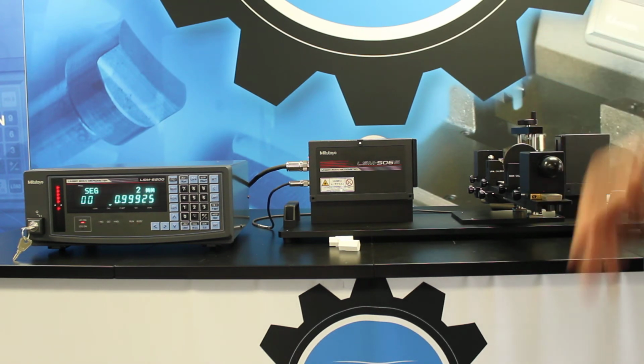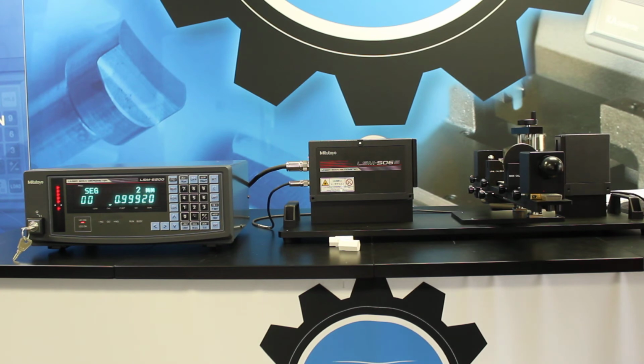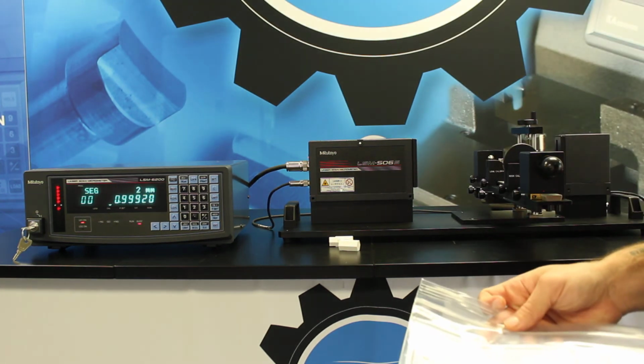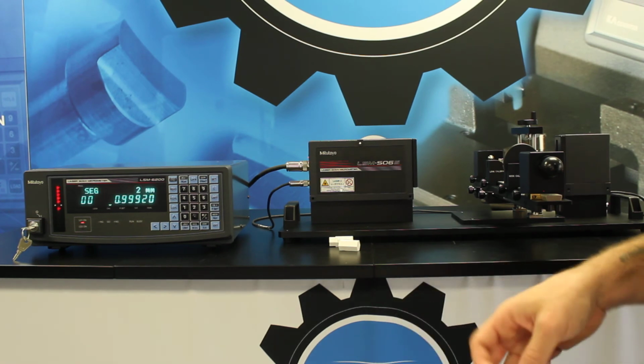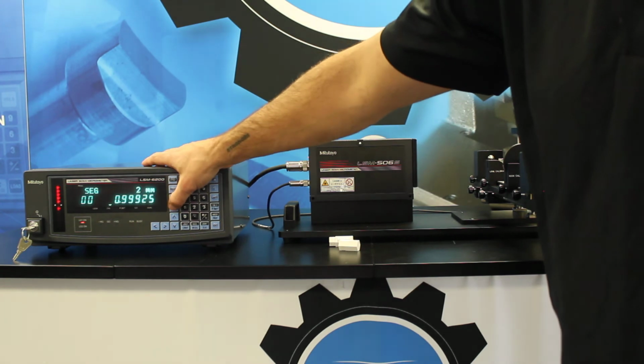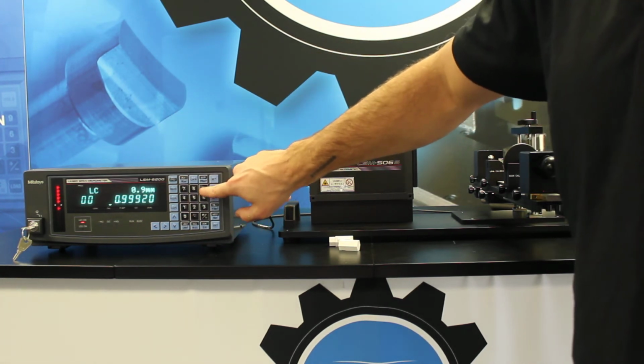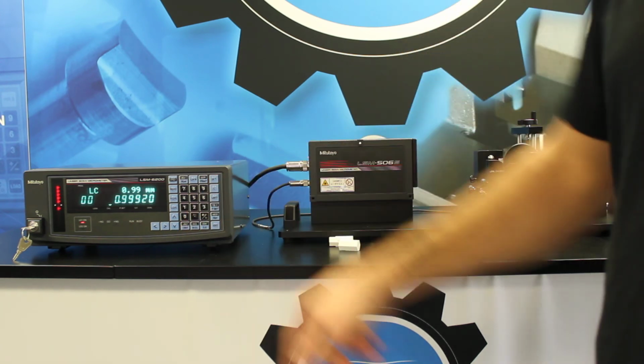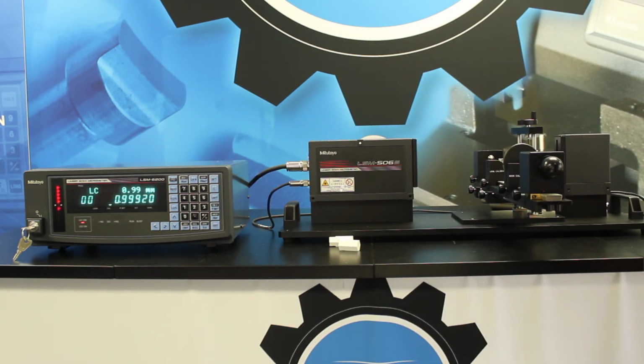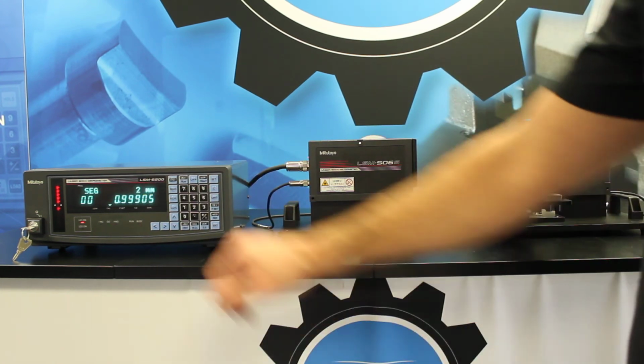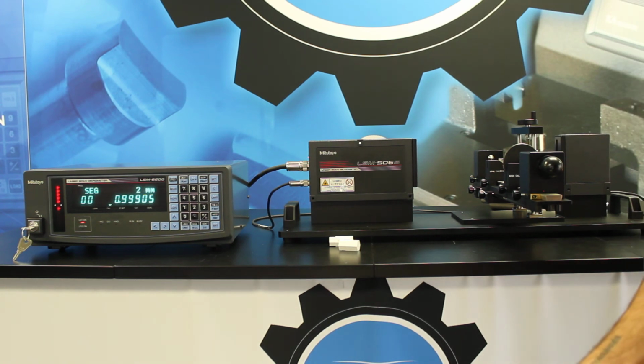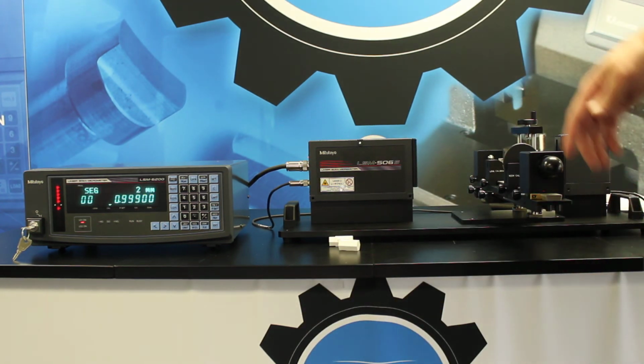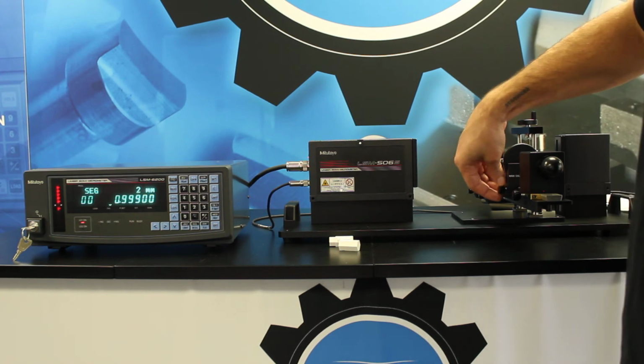I do not need to raise or lower my work stage at this point for the low calibration artifact. My low calibration artifact is calibrated at 999 microns. So now I'm going to press the low cal button, enter in my value of 0.999. Again, I'm going to hit enter. It's going to pause for a couple seconds, read that value, show it on the display. Again, sub-micron, not in a lab environment, but it is holding our value of 999 microns.